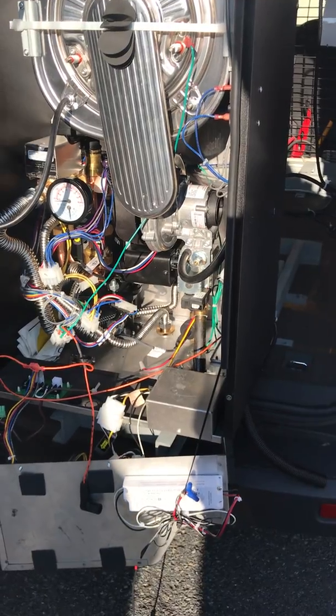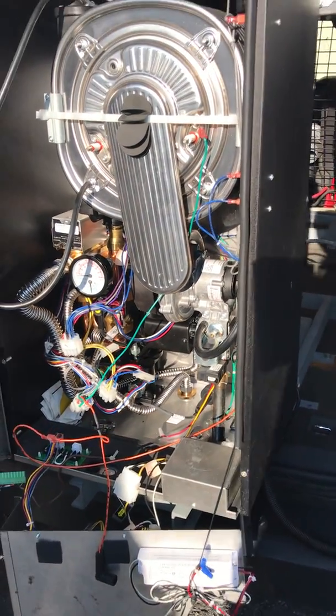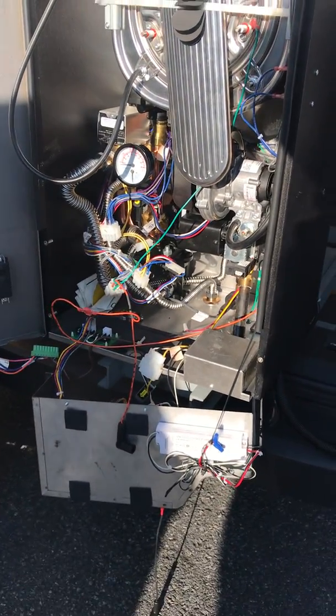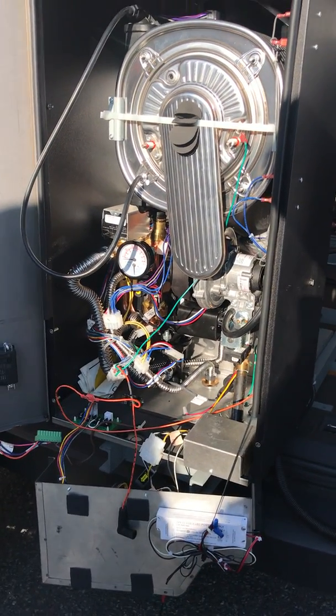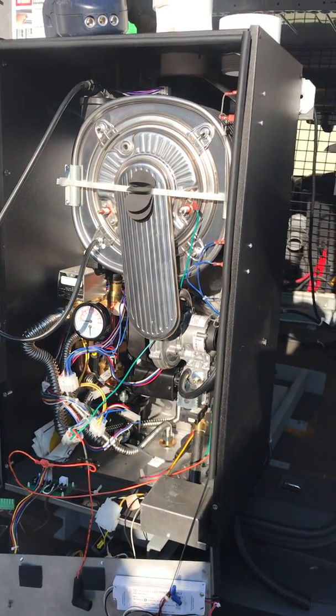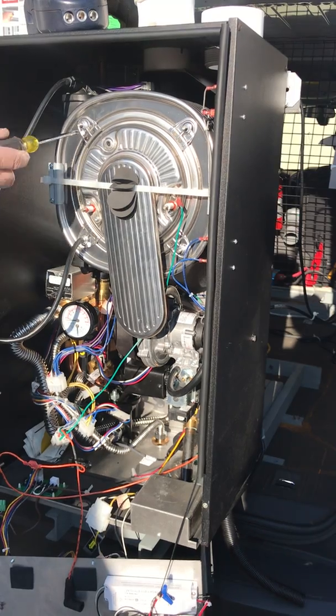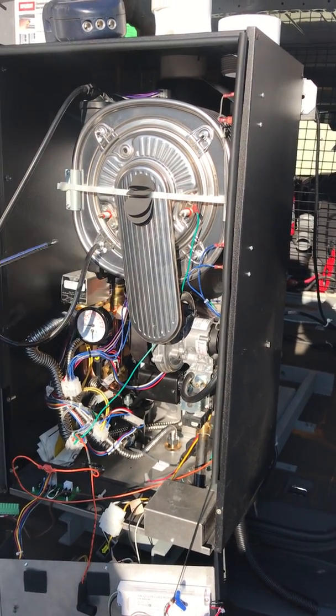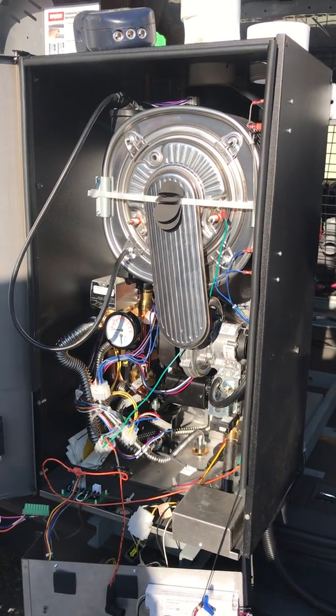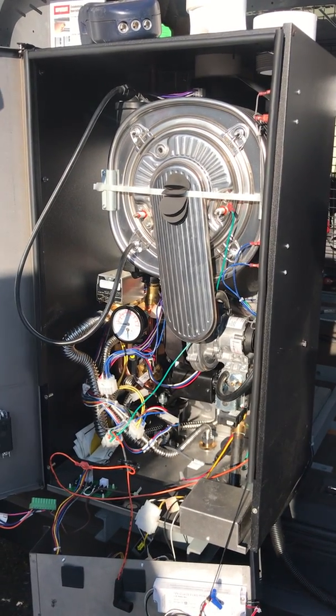And here's what I do. There's a little peep sight. So when you get it fired up and you're doing regular maintenance, I'm looking in and I look for little sparklies on the heat exchanger, which lets me know I have some buildup on there. So I can take these 4 nuts off and the heat exchanger, the burner side pops right out. You don't need any gaskets or anything to put in.